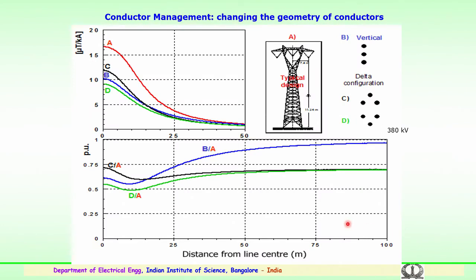The second point was the clearances, height, as mentioned earlier, and the conductor management, which is very important. We have also seen the conductor management going in for different configurations, and the conductors going in for a transposition. This will help in the reduction of fields, or magnetic fields. Here you can see a small typical example of the design of a vertical type of tower or a delta configuration type of tower, how the conductors are managed and connected. This will be helpful. So, various options have been shown here.